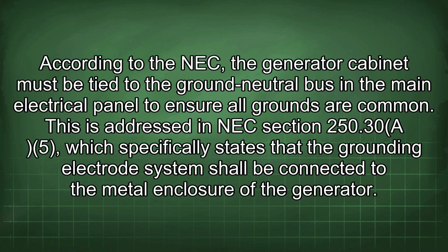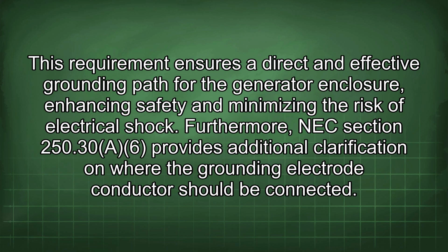According to the NEC, the generator cabinet must be tied to the ground neutral bus in the main electrical panel to ensure all grounds are common. This is addressed in NEC section 250.35, which specifically states that the grounding electrode system shall be connected to the metal enclosure of the generator.